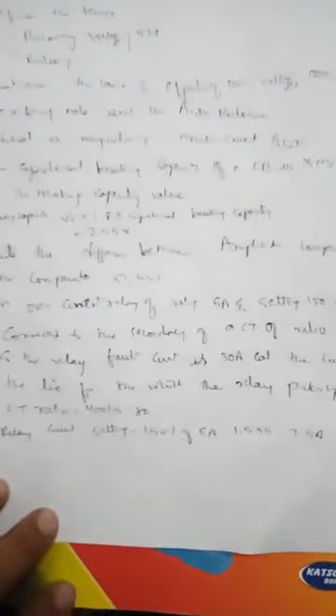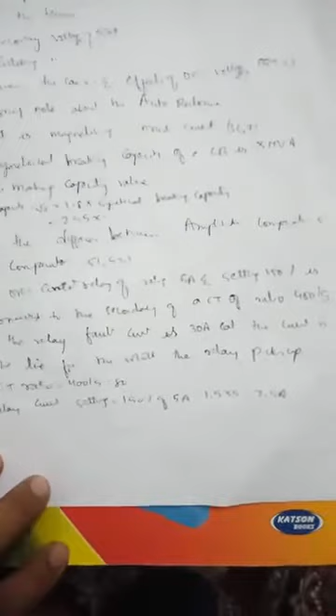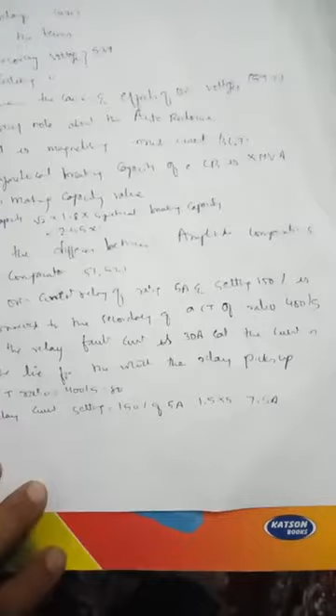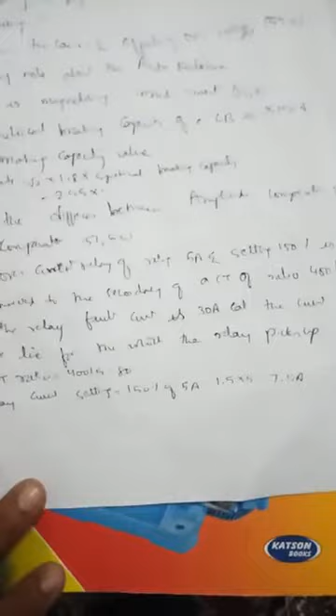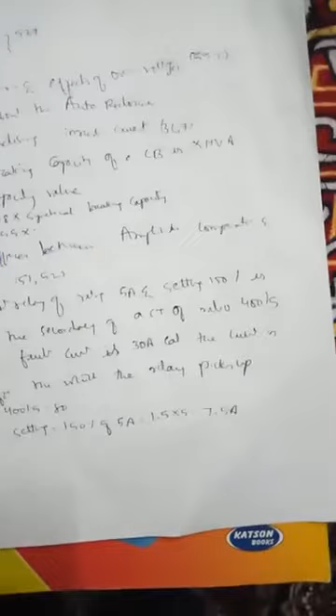Next is a numerical. An overcurrent relay of rating 5 amps and setting 150% is connected to the secondary of a CT of ratio 400 by 5, and the relay fault current is 30 amps. Calculate the current in the line for which the relay picks up. So given is the current transformer ratio 400 by 5, that is 80, and relay current setting is 150% of 5 amps, that is 1.5 into 5, 7.5 amps.